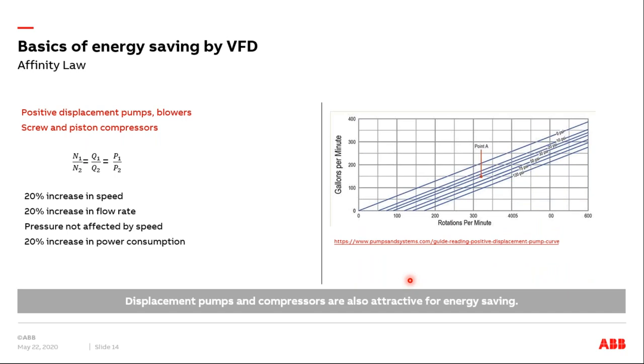So I talked about the centrifugal fan and pump, but there are other types of pumps and blowers and compressors. In this case, you don't have any cubic relation, but you have a linear relationship of the power consumed with the speed of your prime mover. So here it's basically just linear. If you increase your speed by 20%, your flow rate increases by 20%, and your power consumption also increases by 20%. So still it's attractive, but the main attraction for VFD is if you have centrifugal fans and pumps, which are in the majority of cases. The majority of these fans and pumps are centrifugal type.